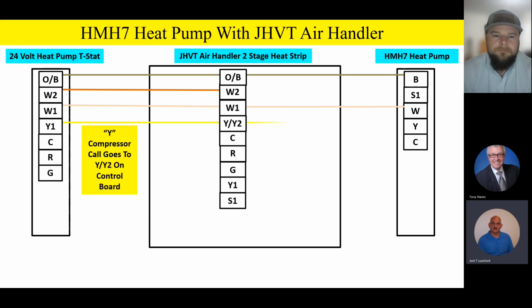Now watch this, Y1 from the thermostat, this is really important, Y1 from the thermostat goes over to the Y/Y2 on the terminal board on the air handler. And the reason we do that, we want to make sure that anytime we have a Y call to the compressor outside, we're going to drive the indoor unit to 100% airflow as the default airflow. So that goes to Y/Y2 on the air handler.